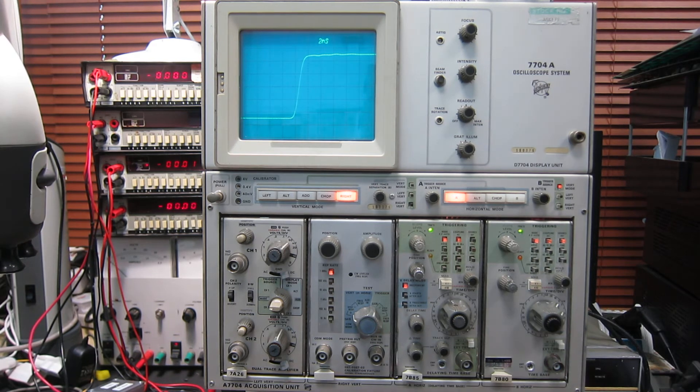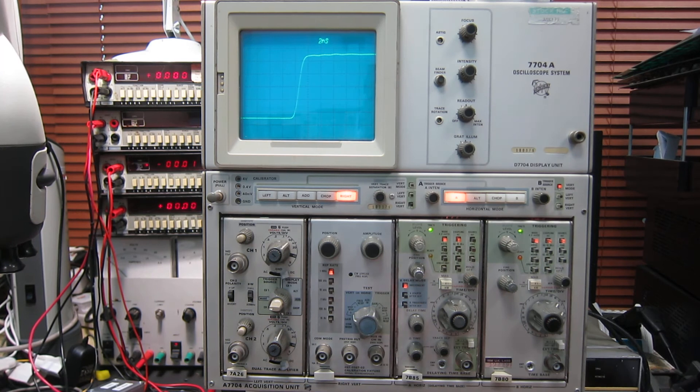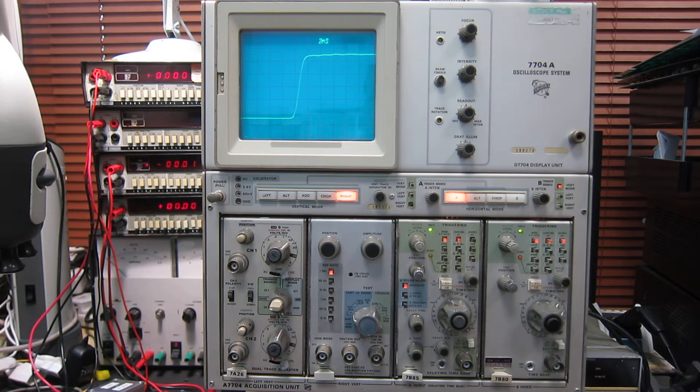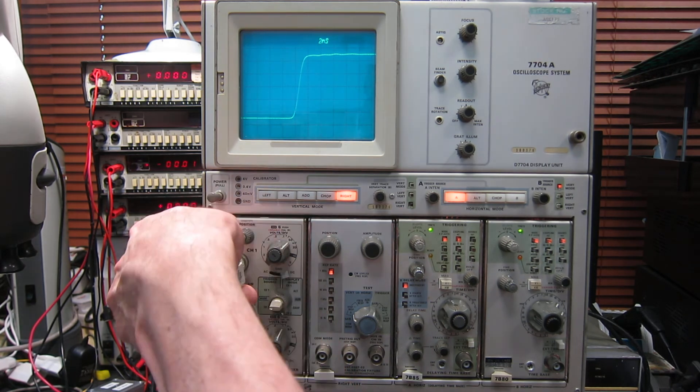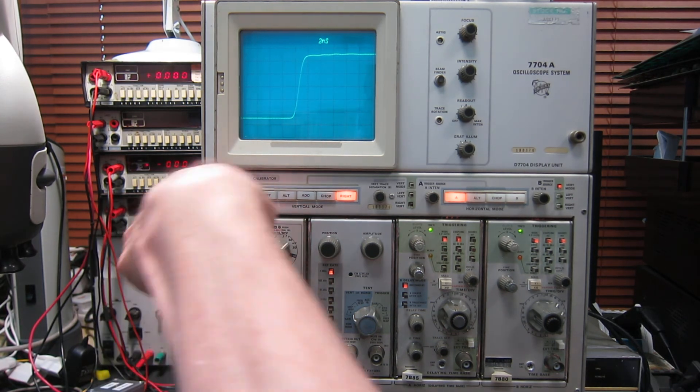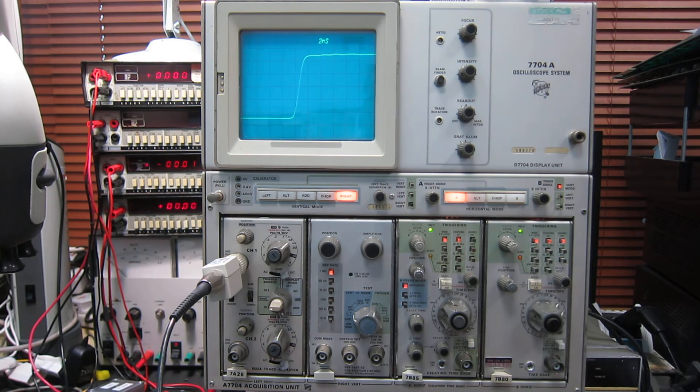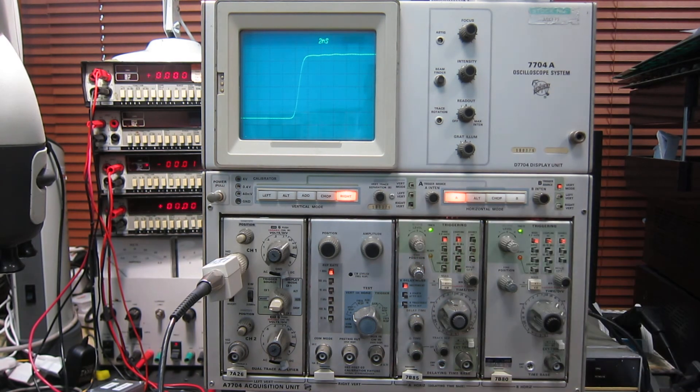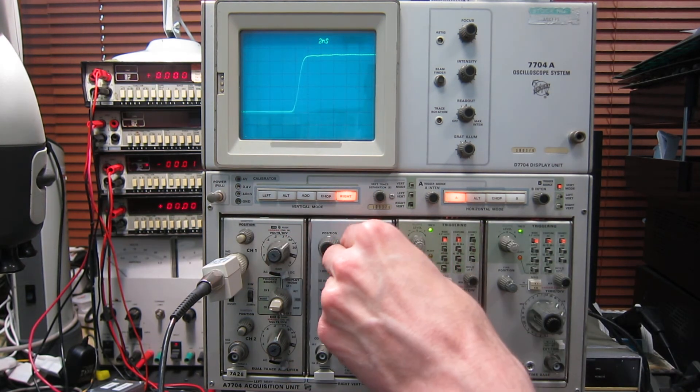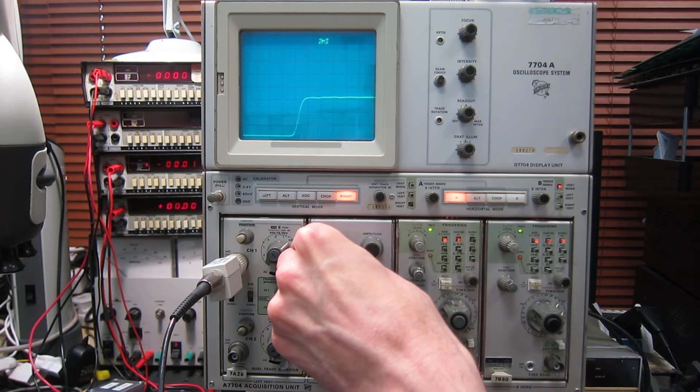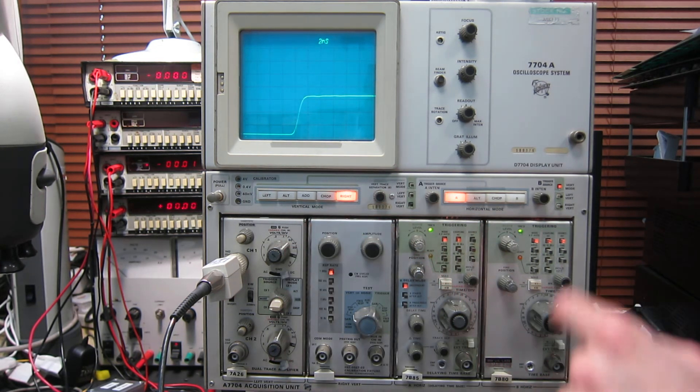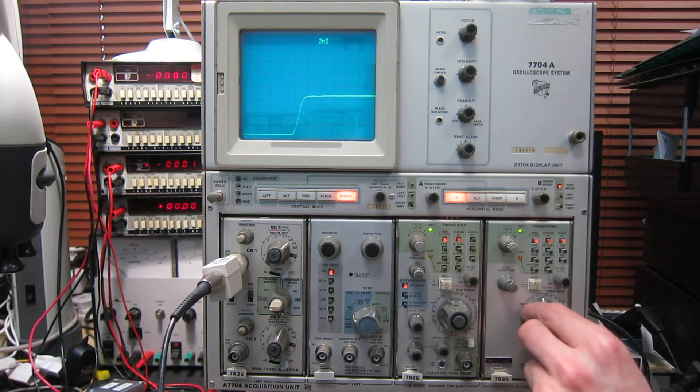What I can also do, because we've now got this extra signal source, I can show you how we can use the two time bases to view two independent signals at the same time on the same screen, which is a good trick that very few scopes can actually do, and it means you've effectively got two scopes in one box. What I'm going to do is use time base A to view the right hand trace, and I'll just shrink it down a bit. Then I'm going to use time base B on an entirely different time base setting.